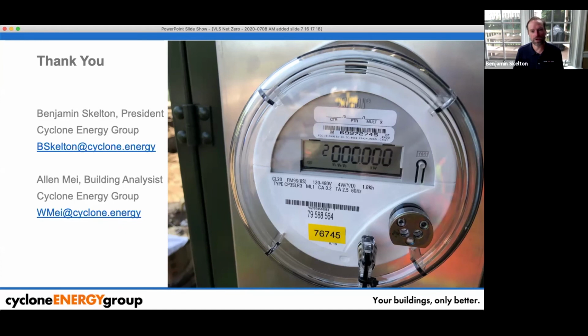We're starting to get more buildings putting in monitoring-based commissioning programs that are fault detection programs, essentially. So they notice when a valve isn't fully closed and it's leaking through, and they sense that the temperature is higher than it should be, or a VAV terminal box isn't working properly. These are extremely popular tools that are going mostly to commercial office buildings right now. In Chicago and the surrounding areas, ComEd incentivizes the installation of that software for the end users, so it's very popular.